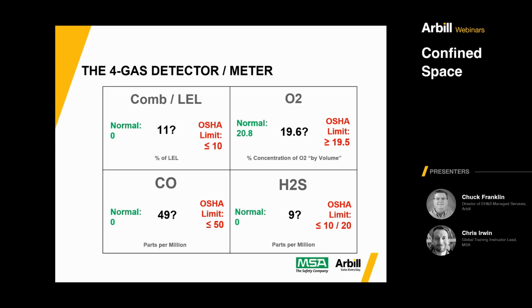I could say the same about all the different things on the screen here. For combustibles, you can see where the alarms go off and what normal should be; same with carbon monoxide and H2S. All these numbers measure something different. O2 is percent of oxygen in the atmosphere. The combustible sensor tells us how close we are to the lower explosive limit for whatever substance is in the air. The other two give us measurements in parts per million—so each one is measuring something specific.